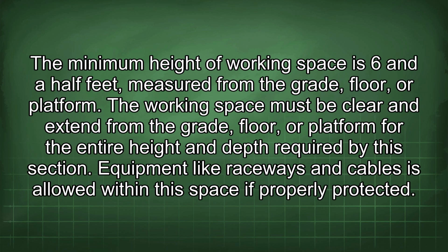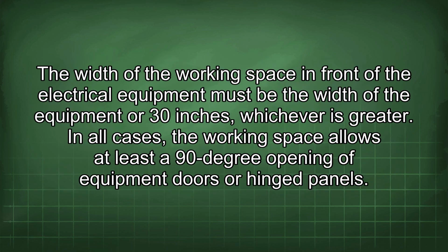The minimum height of working space is 6.5 feet measured from the grade floor or platform. The working space must be clear and extend from the grade floor or platform for the entire height and depth required by this section. Equipment like raceways and cables is allowed within the space if properly protected. The width of the working space in front of the electrical equipment must be the width of the equipment or 30 inches, whichever is greater. In all cases, the working space allows at least a 90-degree opening of equipment doors or hinged panels.